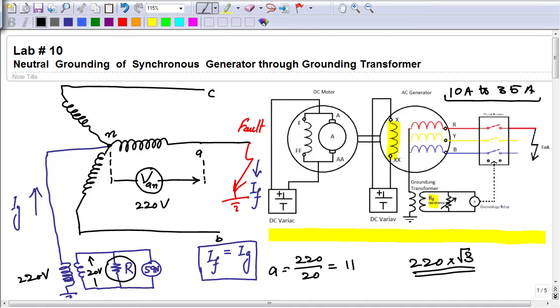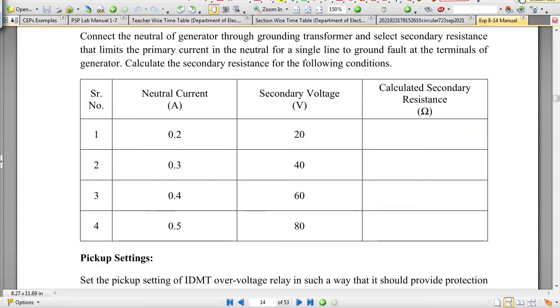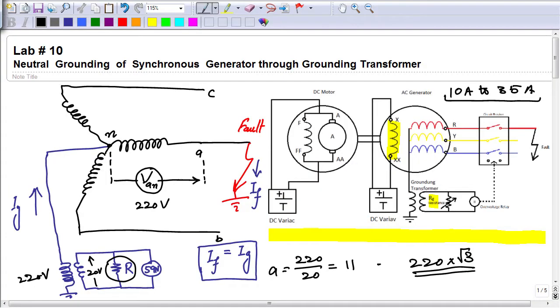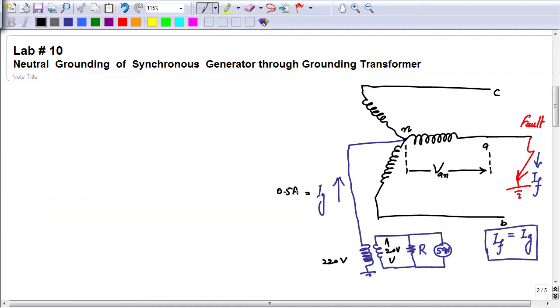For example, in this situation I will assume that I want a fault current equal to 0.5. So if we want to limit the fault current IF to 0.5 ampere, what should be the value in this circuit? The calculations are simple. When a line to ground fault occurs across the terminal of the generator, so this point and this ground, the total voltage that will appear across this primary of the transformer will be equal to the voltage across this phase, line to neutral, that will be 220.